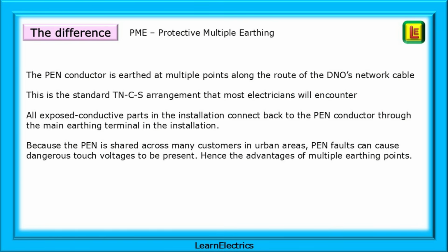So what are the significant differences? Let's begin with PME, protective multiple earthing. The PEN conductor is earthed at multiple points along the route of the DNO's network cable, and this is the standard TNCS arrangement that most electricians will encounter. All exposed conductive parts in the installation connect back to the PEN conductor through the main earthing terminal in the installation. Because the PEN is shared across many customers in urban areas, PEN faults can cause dangerous touch voltages to be present, hence the advantages of multiple earthing points. And please do not get PEN and PME mixed up. PME is an earthing system, a name, a way of doing things, whereas PEN is the actual physical conductor.